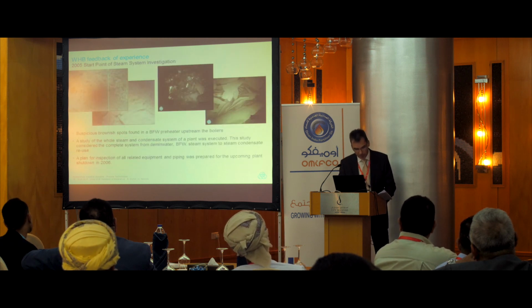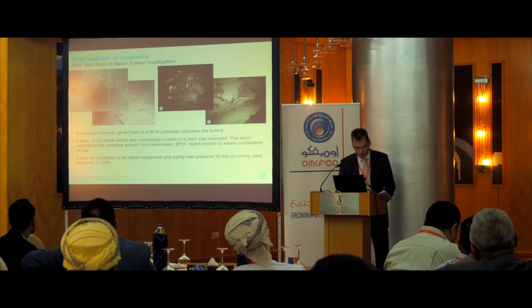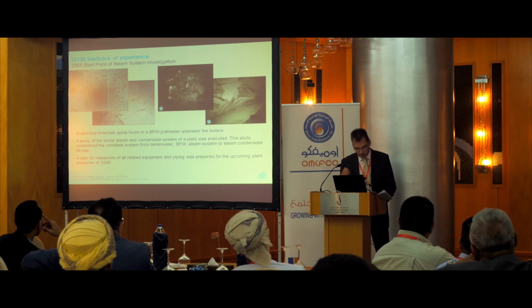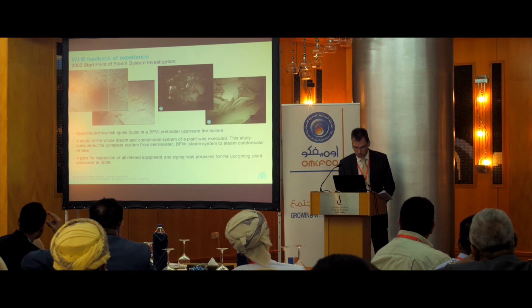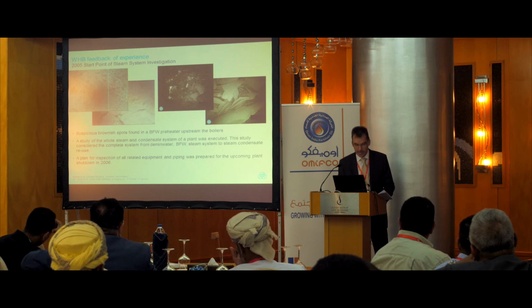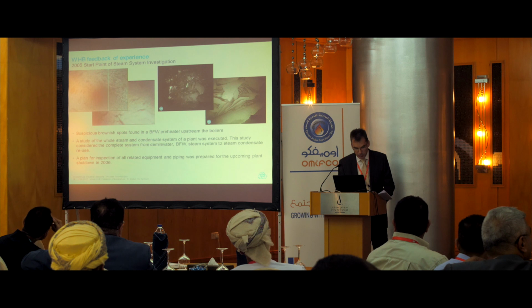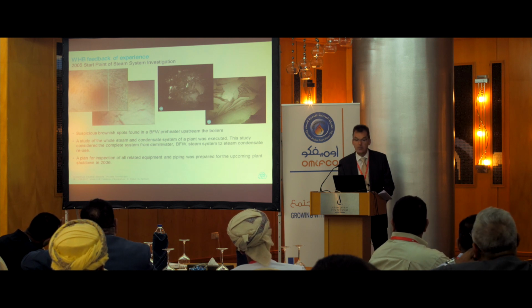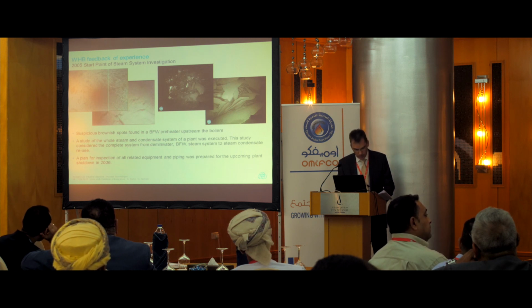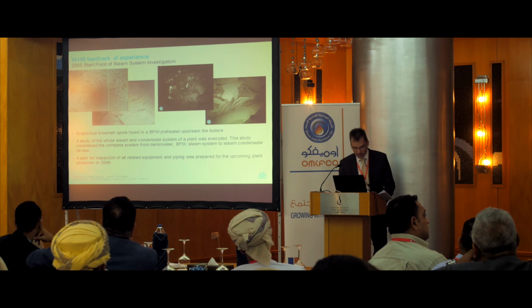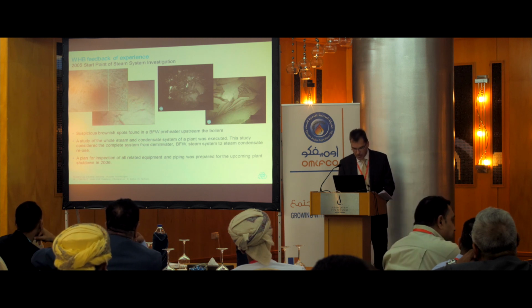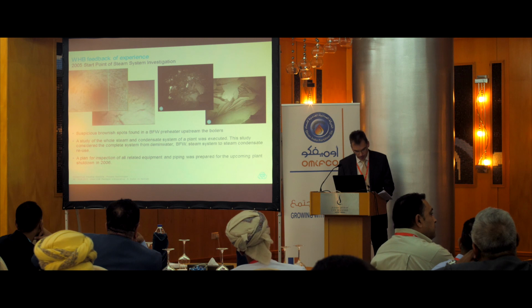In 2005, at one of our plants, a boiler feed water preheater, not a waste heat boiler, a boiler feed water preheater, failed due to tube vibrations. During investigations inside the stainless steel tubes, brownish spots were found, as you can see on the left top side. This is for sure nothing which should be there, especially not inside a stainless steel tube. This was an indication that something is wrong with the boiler feed water and maybe with the steam system itself.